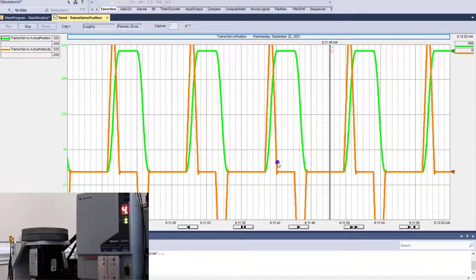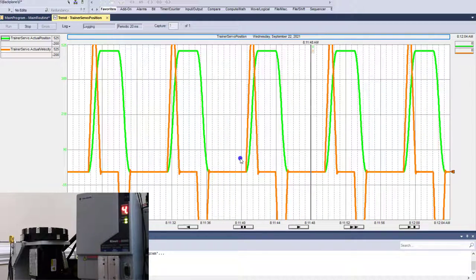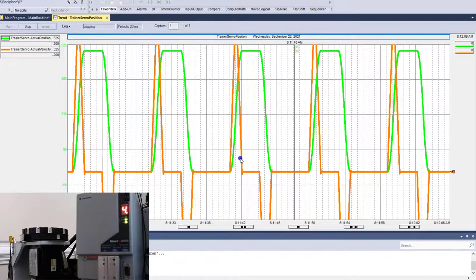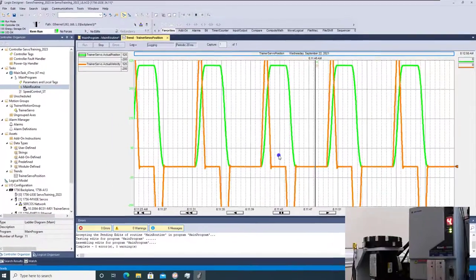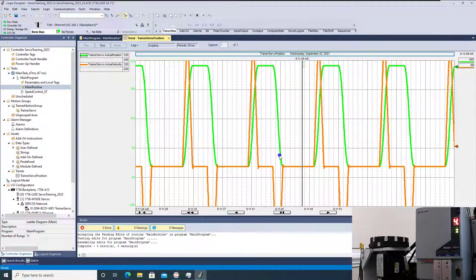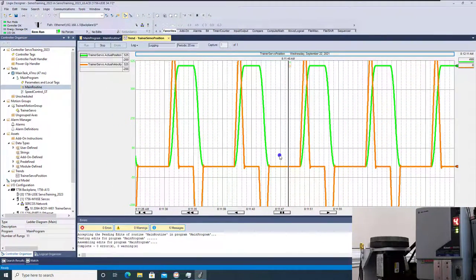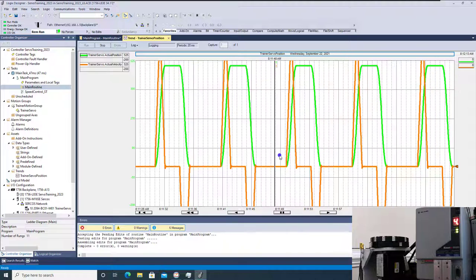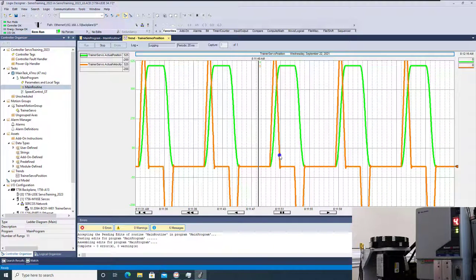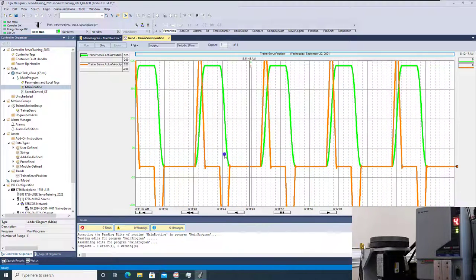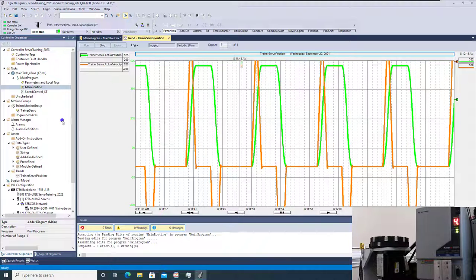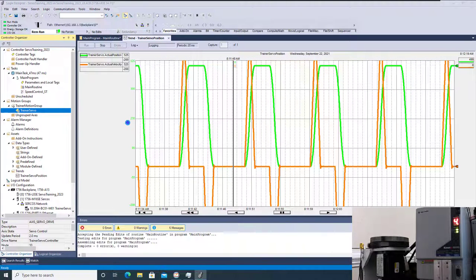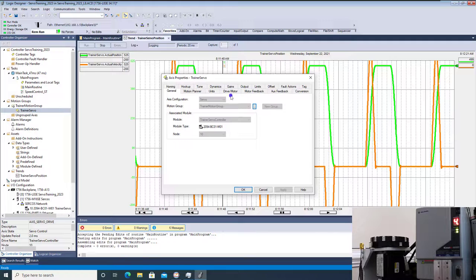But let's just say we had mechanical limitations. Well, we said, okay, well, that's a little bit too, maybe it's moving a heavy load. And then when it tried to move the position, it faults out over position error or something of that nature. Because it does, position error, believe it or not, it doesn't require a lot of position error to actually have that trip.